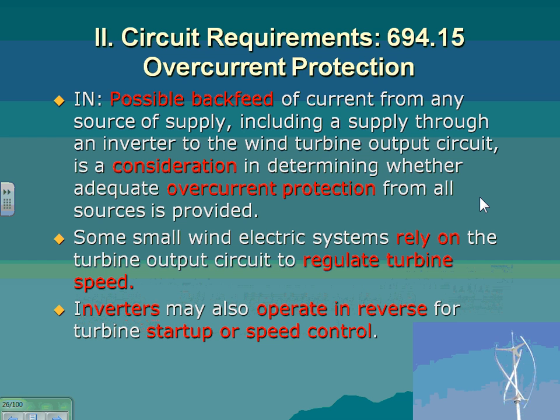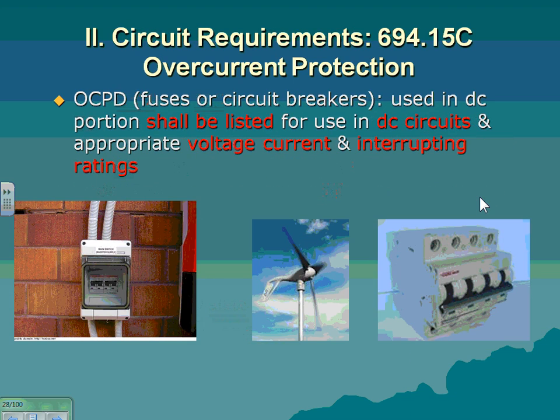Possible backfeed. Backfeed, these disconnects can be energized from both sides. The disconnect of the inverter, the power could be coming directly from the grid or directly from the wind. So the inverter disconnect, the AC disconnect from the inverter, you have to identify it as two sources of power. So if you really disconnect the inverter, on both ends of the inverter could be hot, one from the utility and one from the inverter itself. So it's not just disconnected now, both sides are hot. So you have to have a label there, say, oh, by the way, be careful. Yes, you disconnect the system, but both ends of the disconnect are hot from two different sources. So it talks about this one, overcurrent protection devices shall be listed, the voltage, current, and so forth.